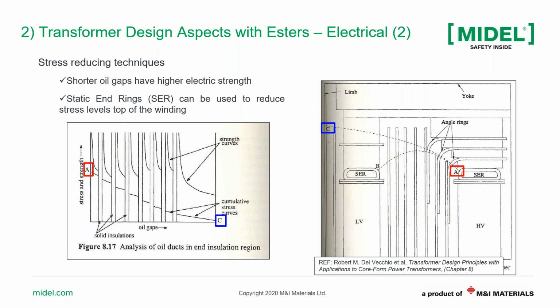So on the right-hand side, you see a transformer schematic. You see the high voltage winding, the low voltage winding. Between them, you have oil gaps separated with pressboard barriers. And you can see point A and point C, and then we have a dashed line, which is the stress line from point A to point C.